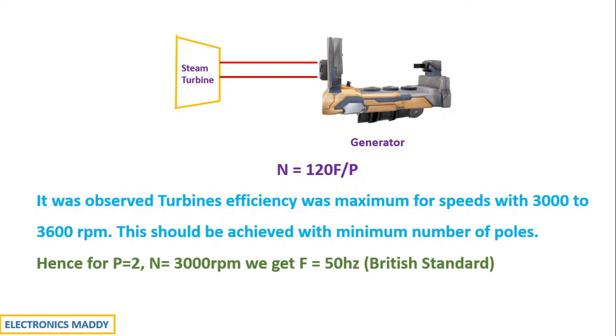With minimum number of poles, say for P is equal to 2 and the speed of 3000 rpm, we get F is equal to 50 Hz according to British standard. And for P is equal to 2, N is equal to 3600 rpm, we get F is equal to 60 Hz according to US standard. This is why we choose 50 Hz or 60 Hz depending upon the country.